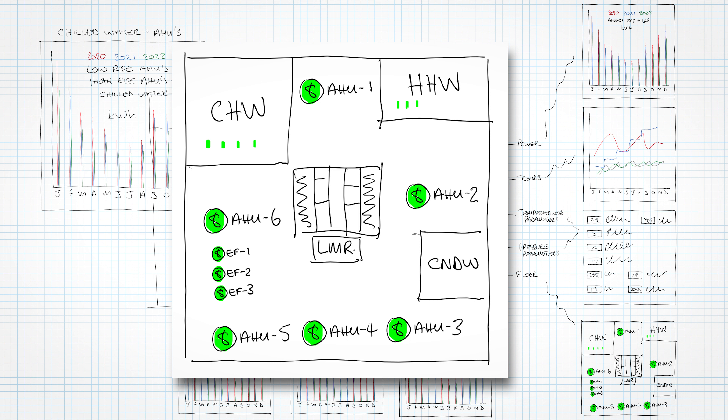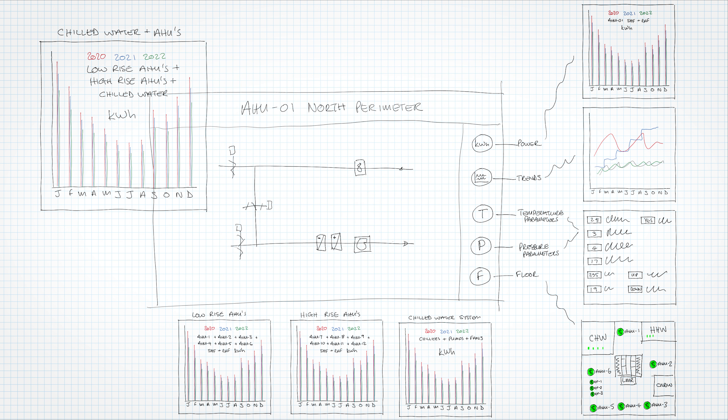It's very useful for a service technician called out to a site they don't know - they can click that floor icon and see exactly where the AHU is. It's not hard to do. On the little floor plan of the plant room, you can see chilled water, hot water, condenser water, and in the middle is AHU 1. Our customers can't see code or database, so if you create this simple graphic and show the facility manager, they can see they're getting something for their money.